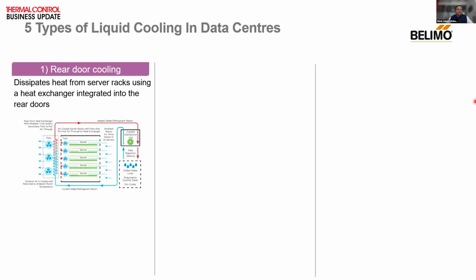There are five types of liquid cooling in a data center. First type is rear door cooling, wherein there is a rack and there is a rear door to which the chilled water is supplied, and then it exchanges the heat from the servers to outside the servers.